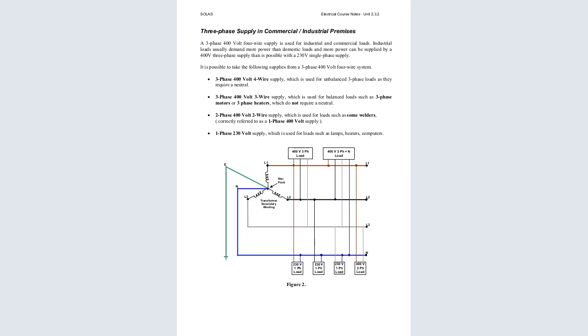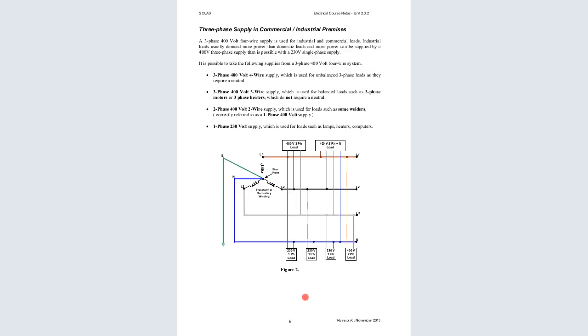So the three-phase 400 volts 3-wire, I said 3-wire is delta. Delta looks like a triangle. We talked about that last week. Delta, that is the 3-wire supply, does not have a neutral wire. But the three-phase star enables the tapping of the neutral. That is why it is normally liked and mostly used, compared to the delta, which does not provide the neutral.